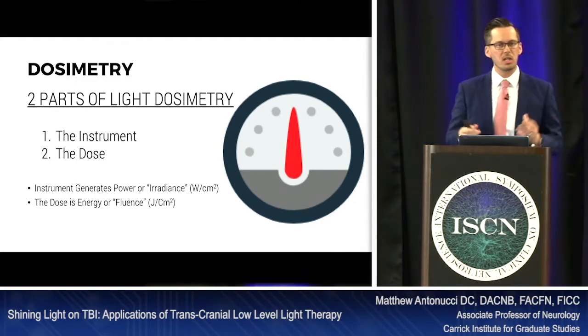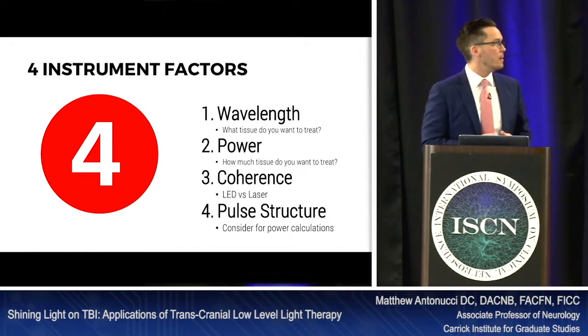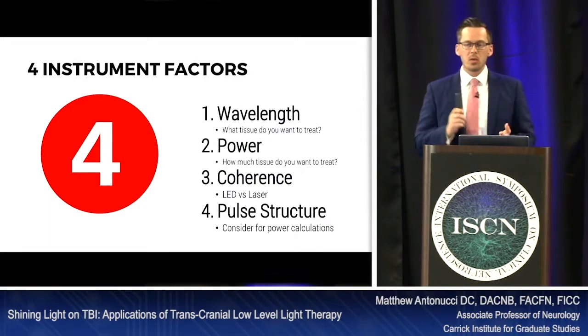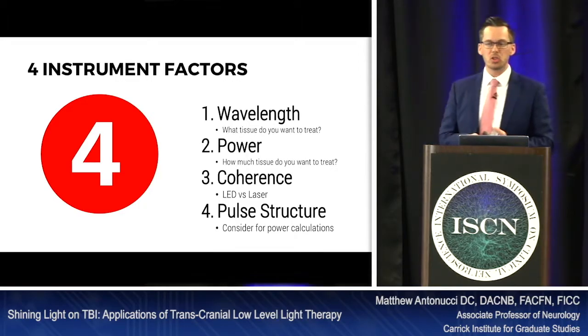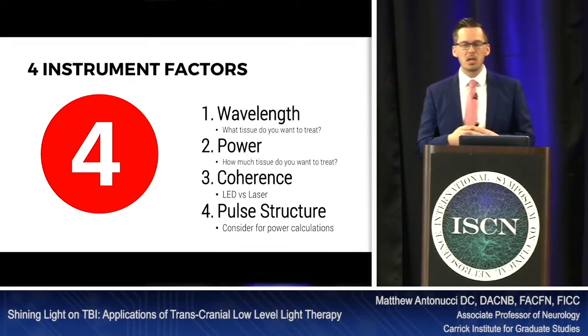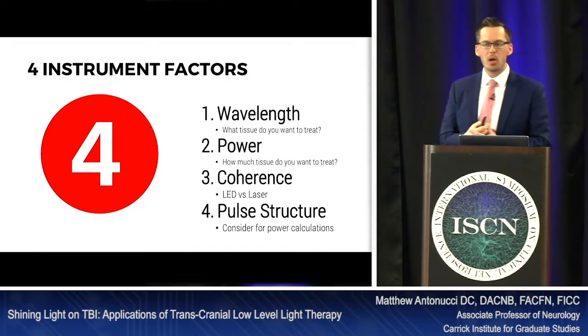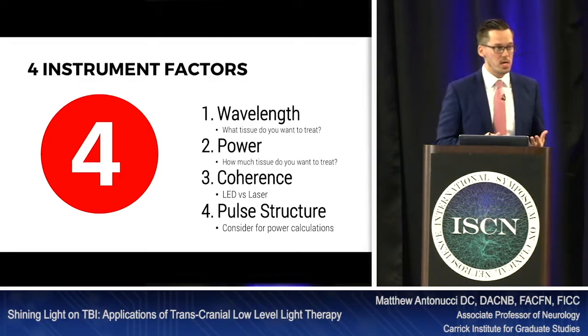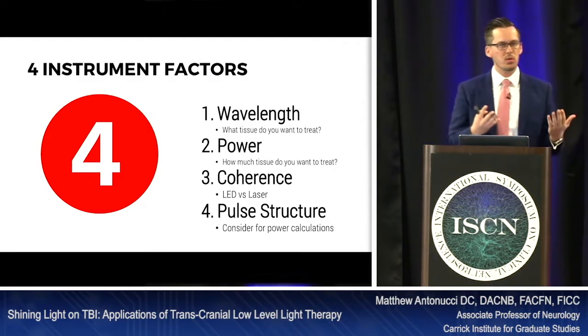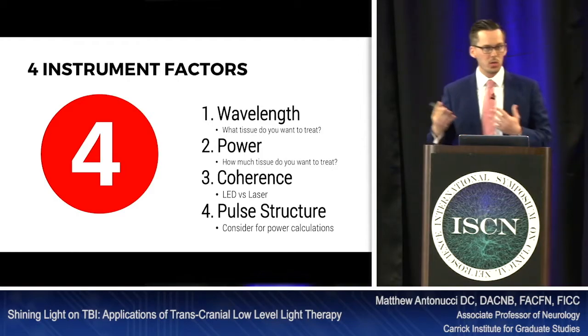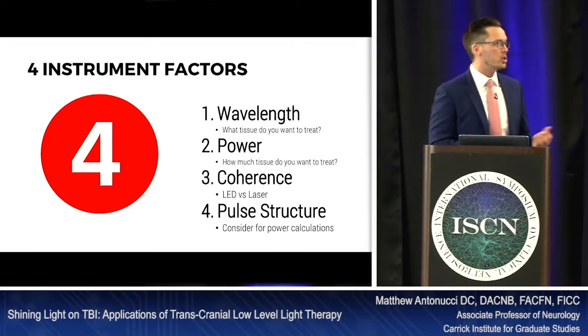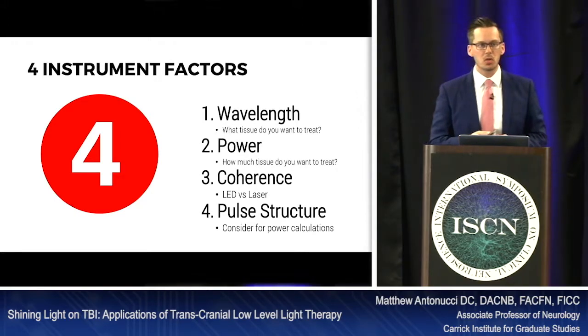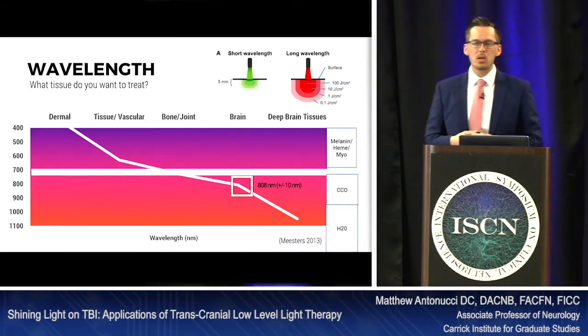When looking at an instrument, there are four factors to consider: wavelength, power, coherence, and pulse structure. The wavelength tells you what tissue you want to treat. Power tells you how much tissue you want to treat. Coherence helps you decide whether to use a light-emitting diode or a laser. And pulse structure is important for power and dose calculations.